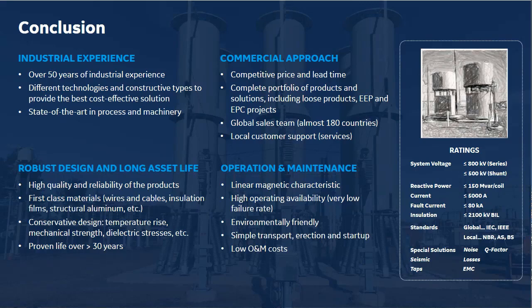For very large reactors, let's say HVDC or power flow reactors, these are very high power, and yes, the losses can be very high. As we cannot change the material that we are using, for example, yes, we could use copper instead of aluminum, but just by adding copper to the design, that would increase the price by 3 times, just because copper is extremely expensive. So the other way to change the losses of the reactor would then be to make it more efficient by changing the type or technology of the wires that go inside of it.